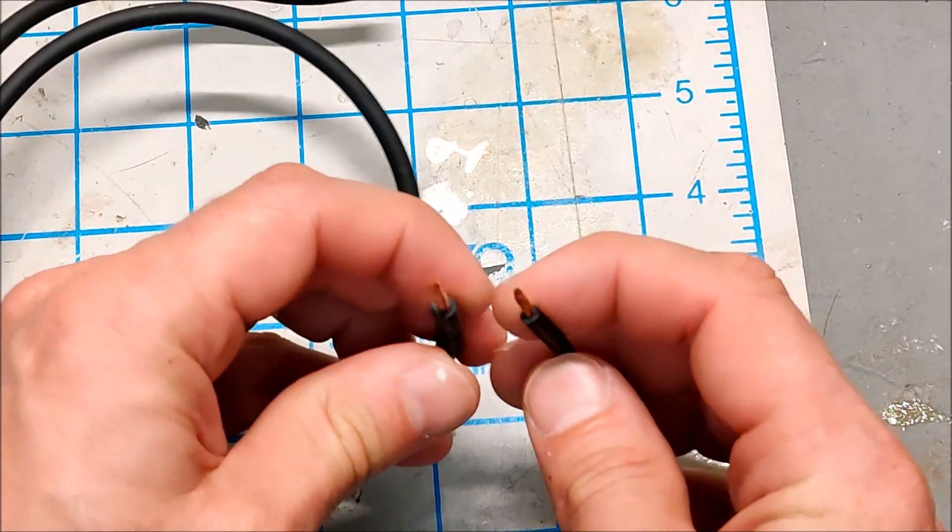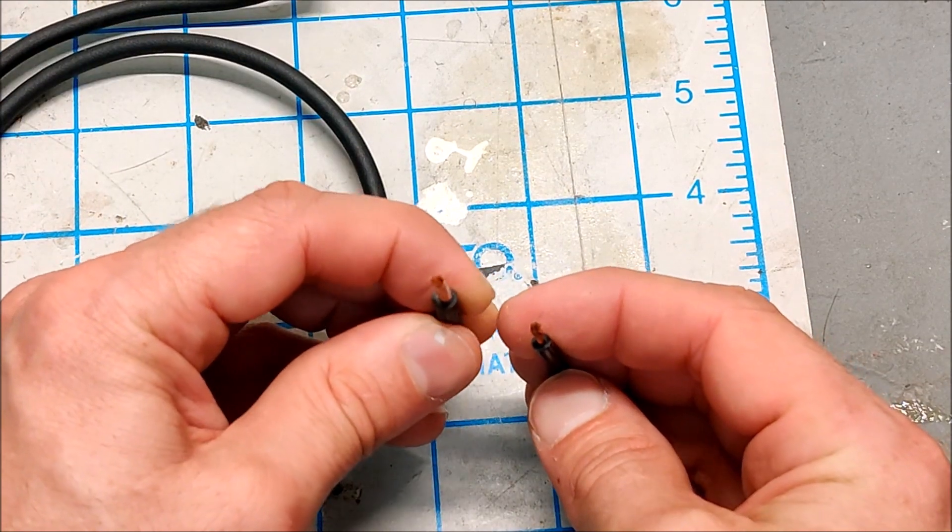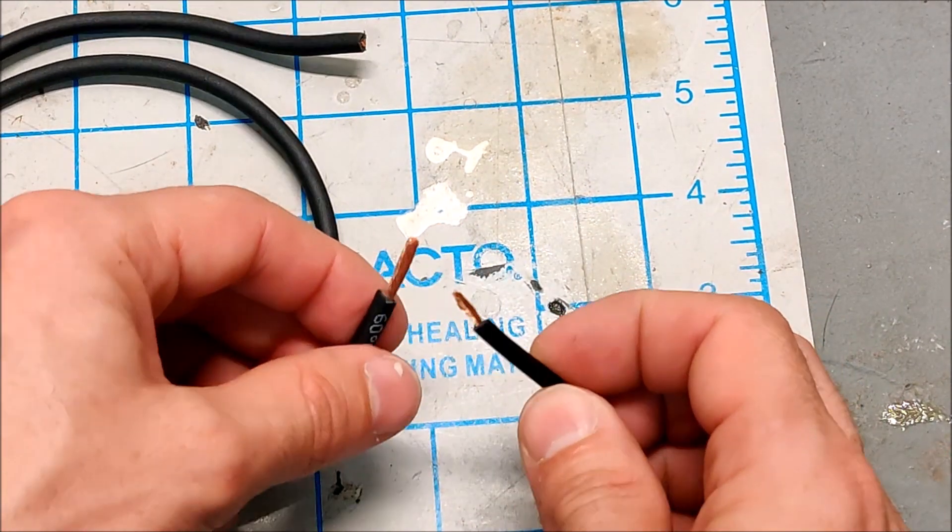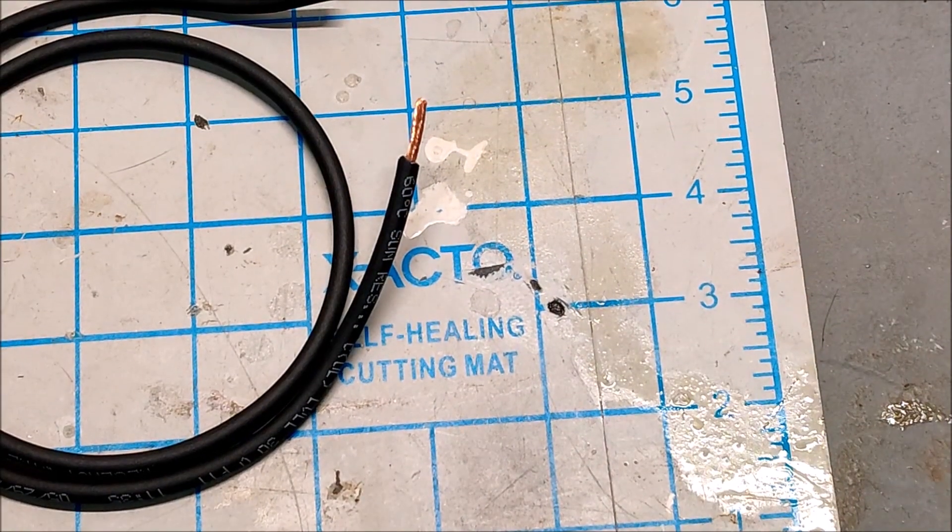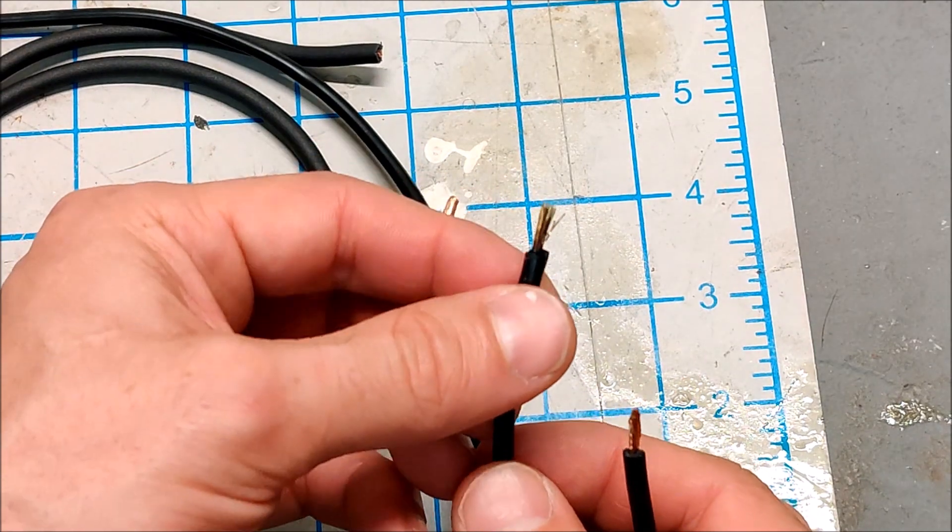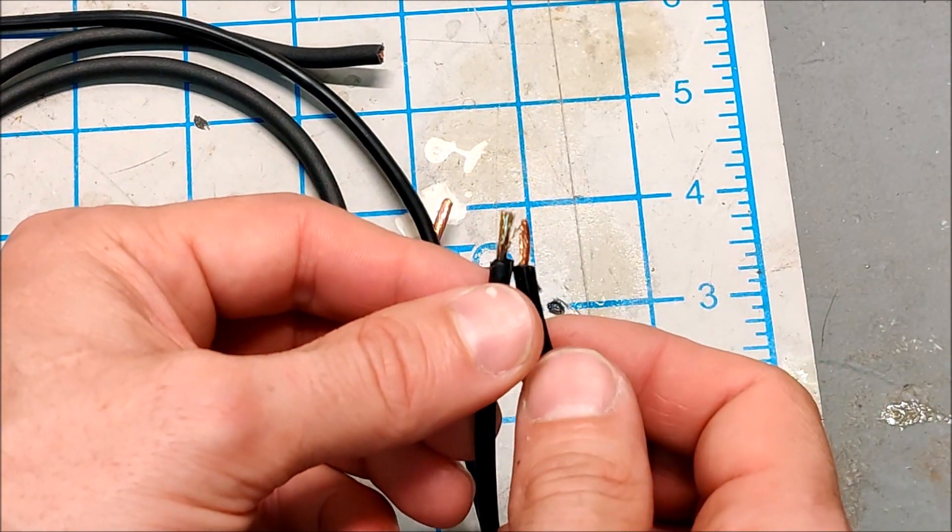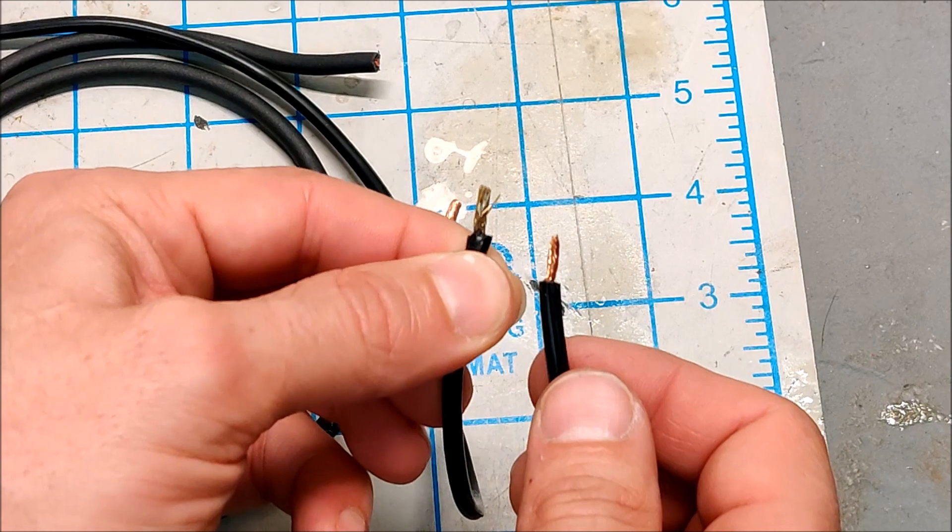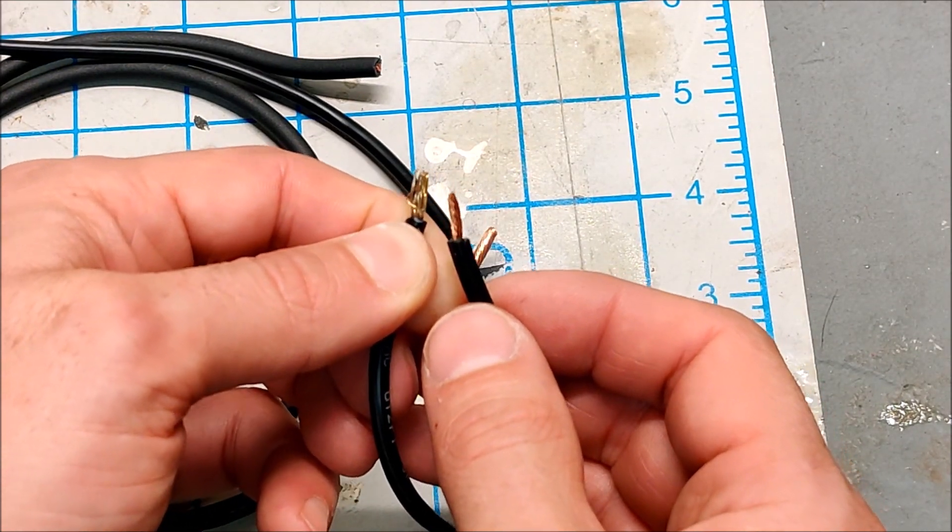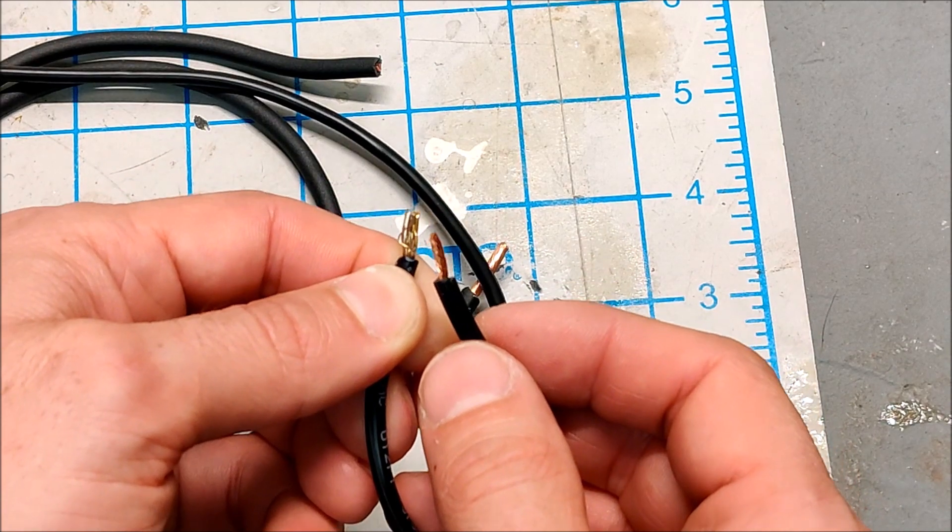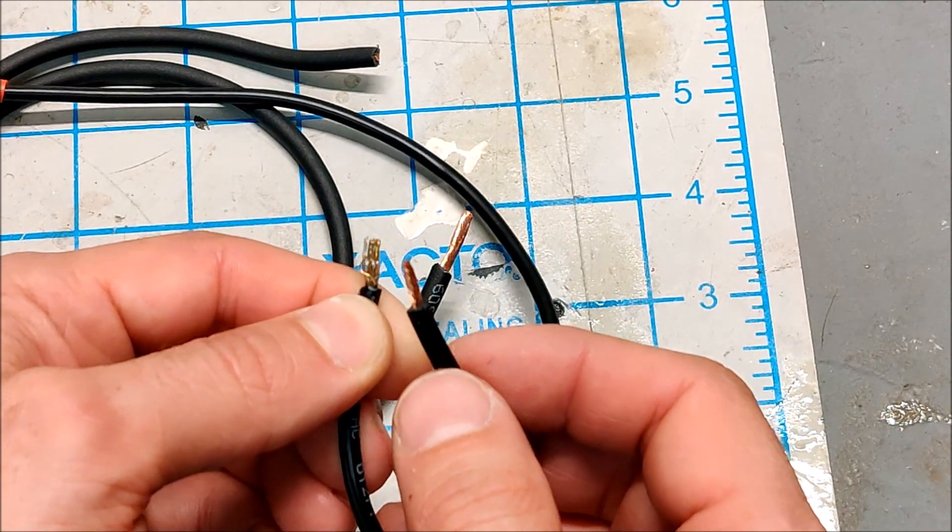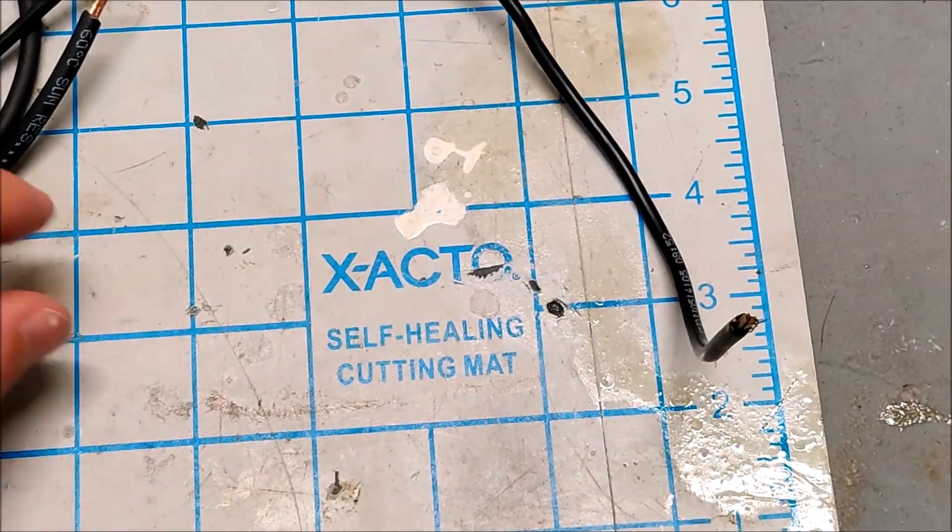They have such thick jackets on them that it's kind of misleading as to how thick the wires are. Here's something very interesting. This wire was attached to the bus bar. Do you see the discoloration in the copper? That's from heat. This wire was getting severely heated and damaged, so good thing I caught it now.